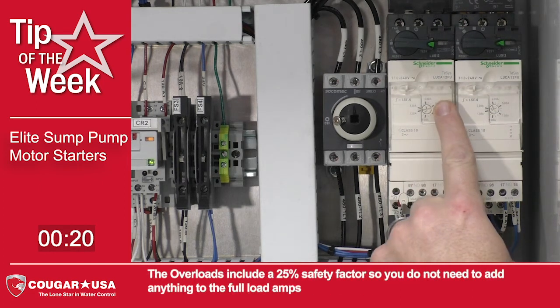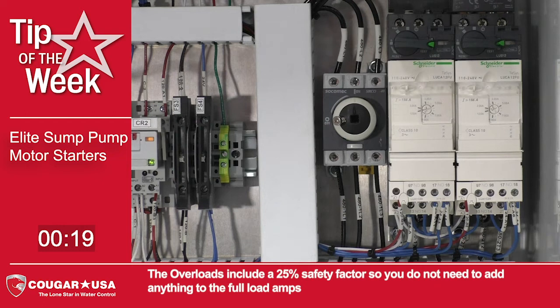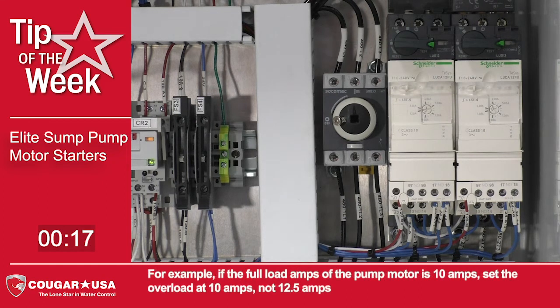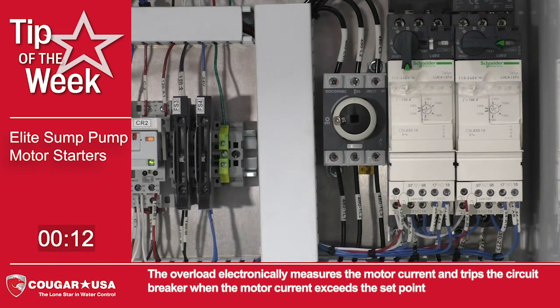amps. The overloads include a 25% safety factor, so you do not need to add anything to the full load amps. For example, if the full load amps of the pump motor is 10 amps, set the overload at 10 amps, not 12.5.